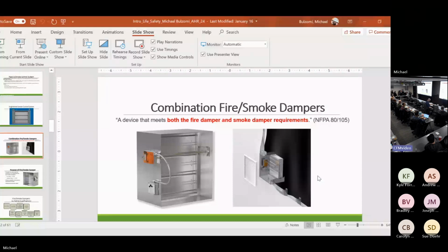UL listing is void. So we always put this sentence in as a damper manufacturer. We'll write a letter and at the very end of it, we'll say, subject to the approval or at the discretion of the authority having jurisdiction. The AHJ has the final call. Doesn't matter what the building code says, what the intent is. If that AHJ accepts it, he accepts it, or she accepts it, or they deny it, they deny it.